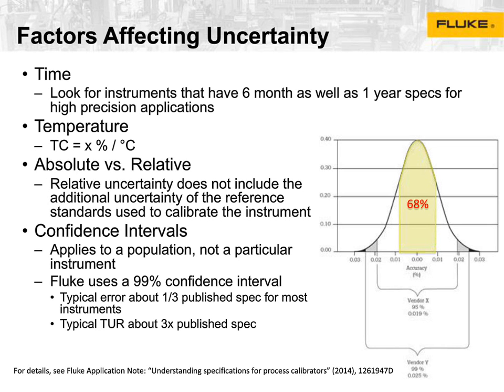Most manufacturers will say that, hey, this gauge is 23 plus or minus 5, 23 plus or minus 20, 23 plus or minus whatever. And then as soon as you get outside that range, you need to calculate an additional error. And if you're in a high accuracy application and you're trying to do something in the bitter, bitter cold or the extreme heat, you need to think about, well, okay, do I need to compensate for accuracy? If you're doing something simple like setting a limit switch, it might not be necessary. But if you're doing something like calibrating a custody flow transmitter, yeah, you probably need to do it.